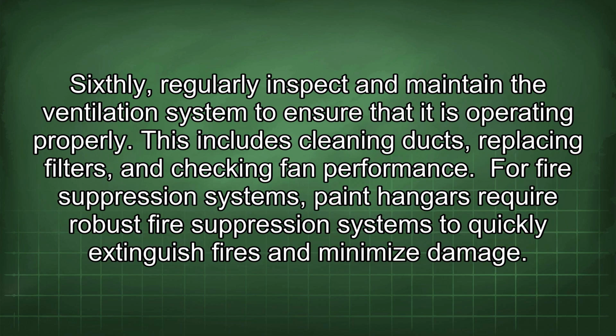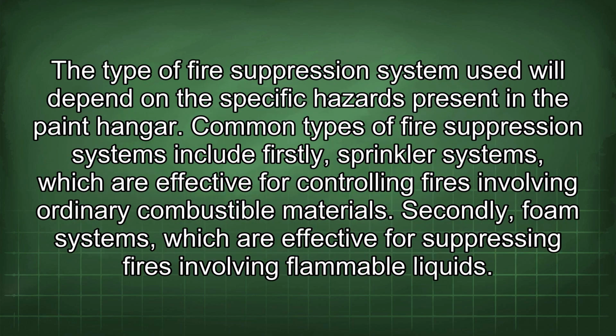Sixthly, regularly inspect and maintain the ventilation system to ensure that it is operating properly. This includes cleaning ducts, replacing filters, and checking fan performance. For fire suppression systems, paint hangars require robust fire suppression systems to quickly extinguish fires and minimize damage. The type of fire suppression system used will depend on the specific hazards present in the paint hangar.